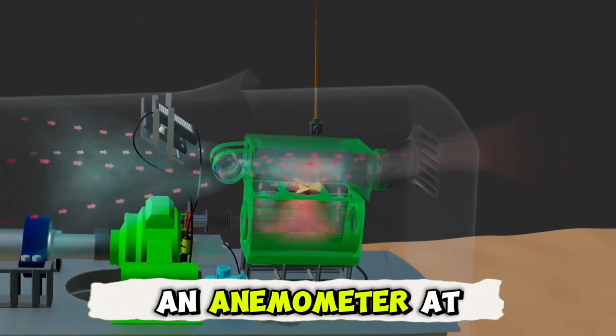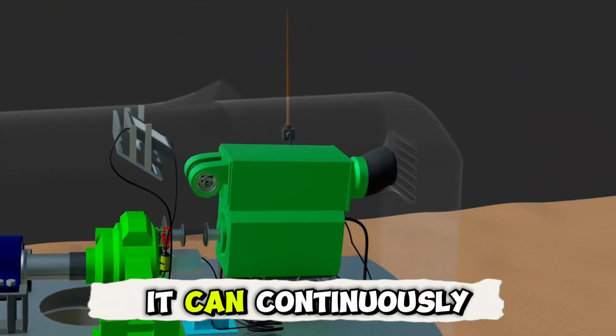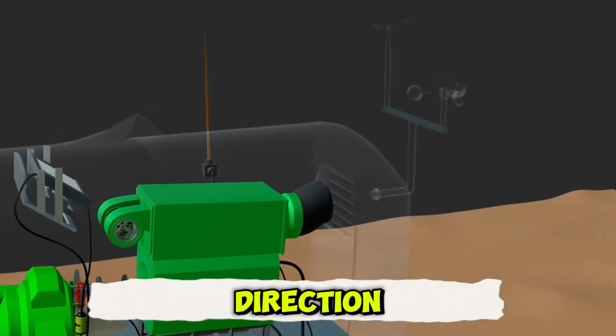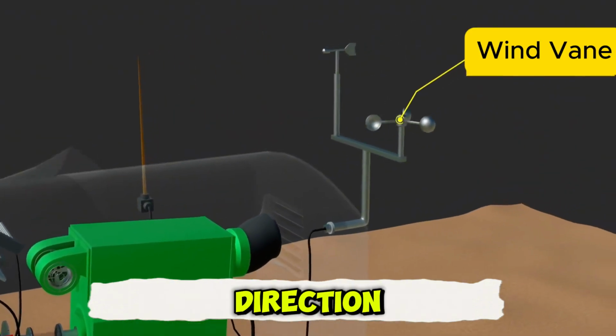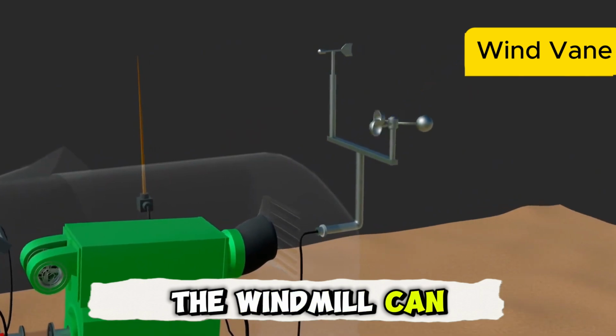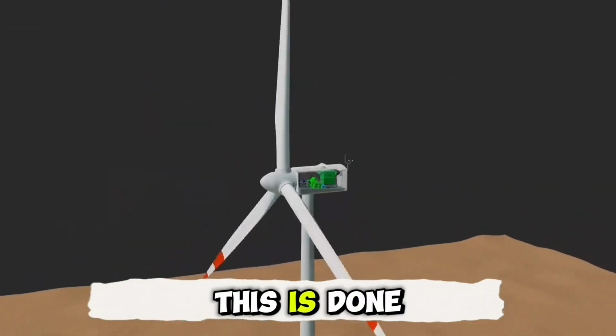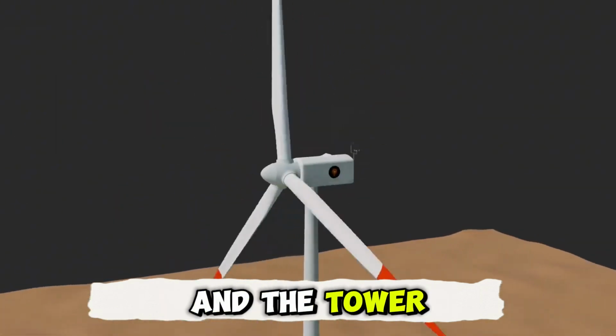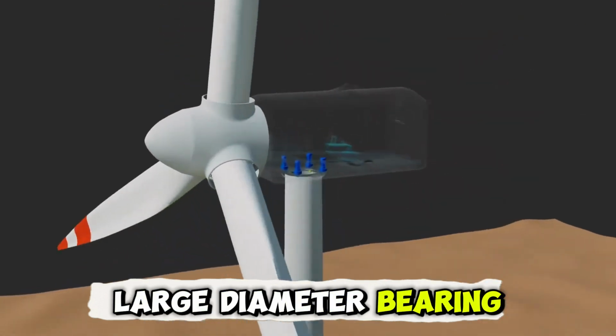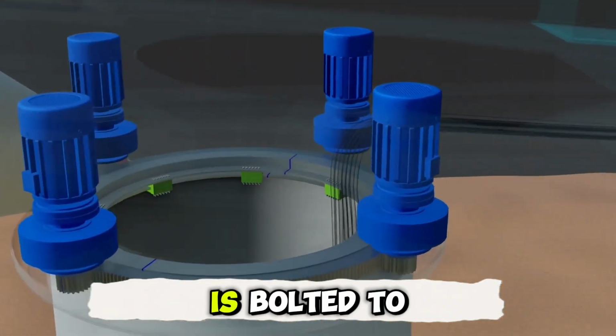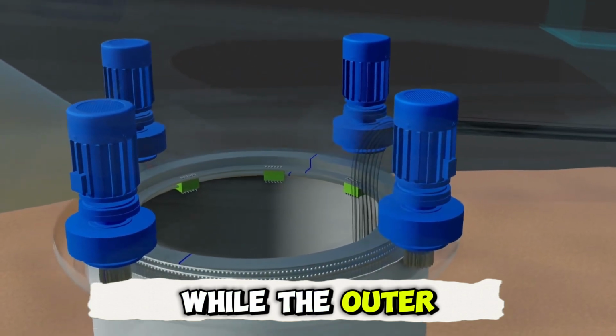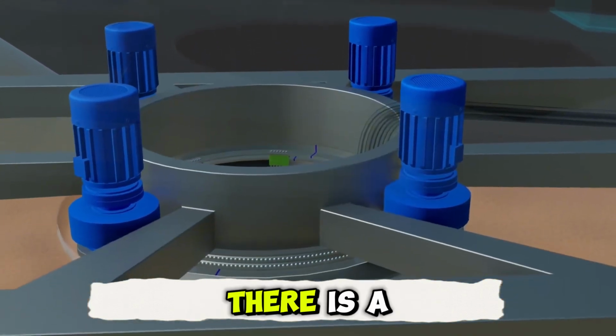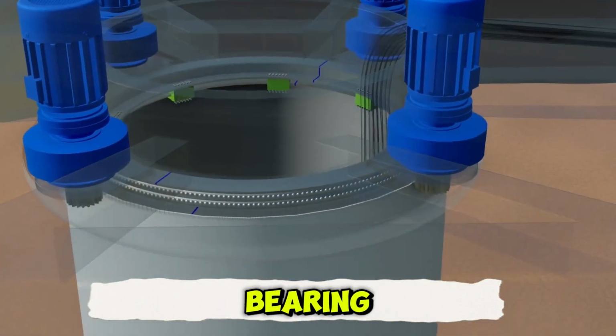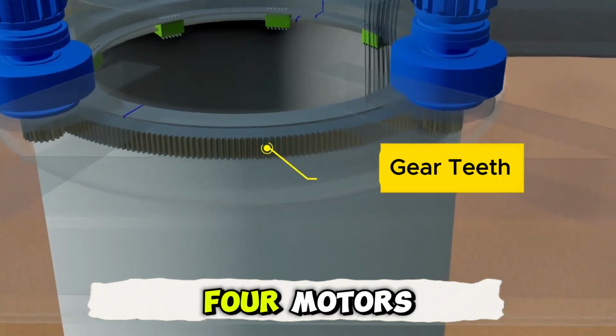There is also an anemometer at this position. It can continuously detect the wind direction, and then, based on the wind direction, the orientation of the windmill can be adjusted. Let's see how this is done. Between the base and the tower, there is a large diameter bearing. The inner ring of the bearing is bolted to the base, while the outer ring is bolted to the tower. There is a ring of gear teeth outside the bearing. It meshes with the gears of 4 motors.